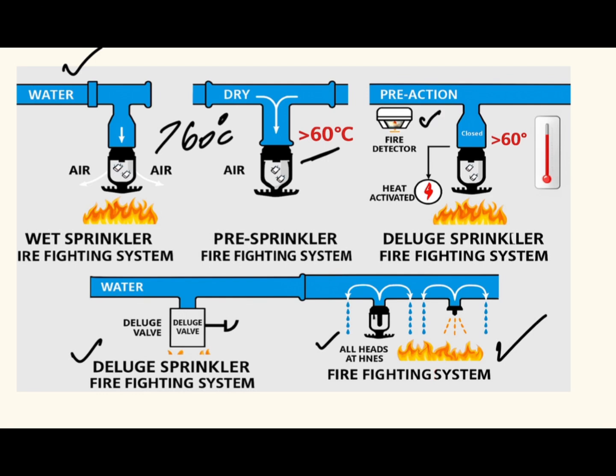Pre-action, we have two trigger mechanisms. One is a fire detector and second is heat activation, right? So here we have better control. If these two conditions are met, then the system will discharge the water. But it is also the same as dry. Here we have air filled in.